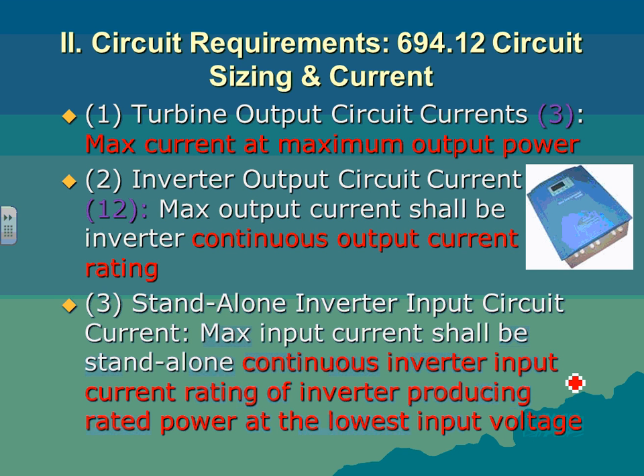Inverter output, maximum output current shall be, the inverter shall be considered continuous. Remember that 125, that magic number, that's where you get your 125. Standalone system, input circuit, maximum input current shall be a standalone continuous inverter input rating of the inverter producing rated power at the lowest input voltage. If you have a standalone, they want the maximum current to be at the lowest voltage, because the lowest voltage in a power system produces the highest current, right, in any power system.